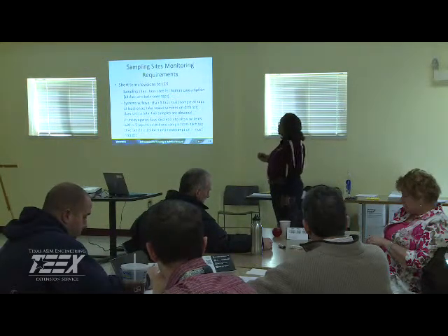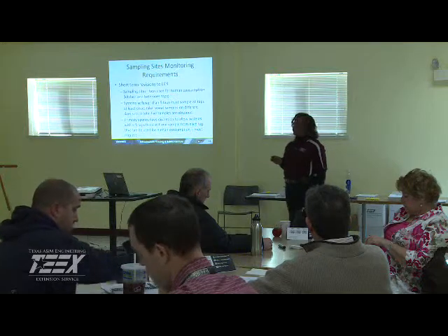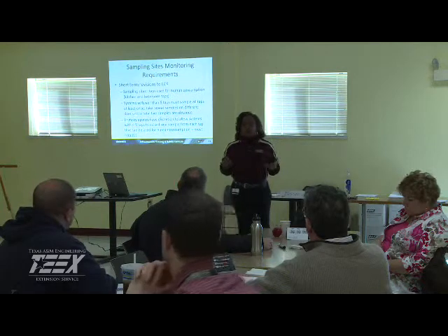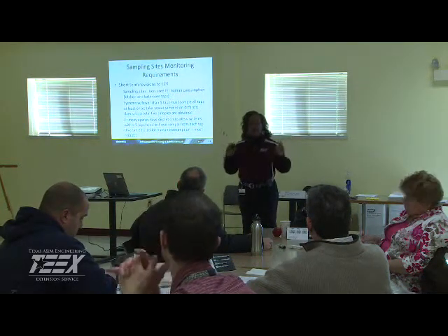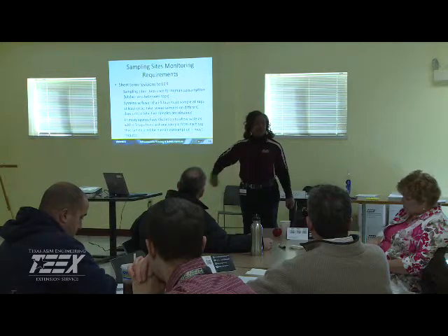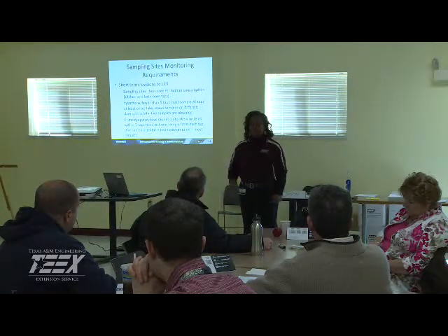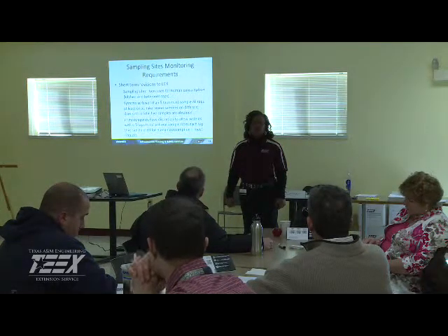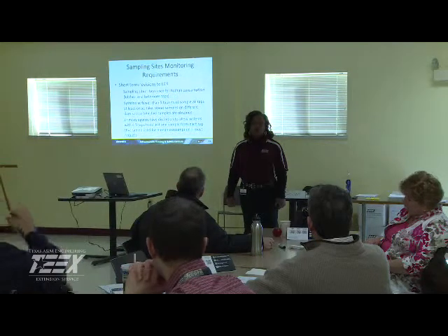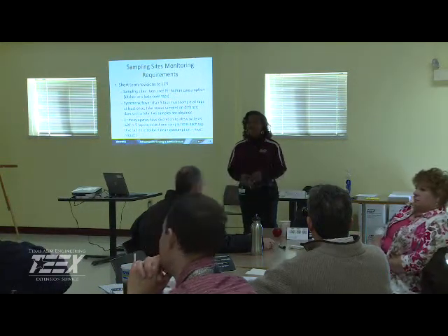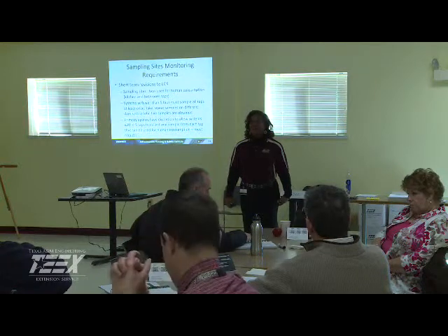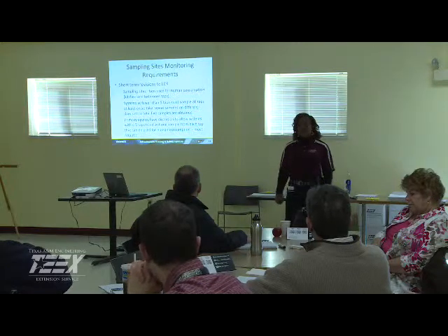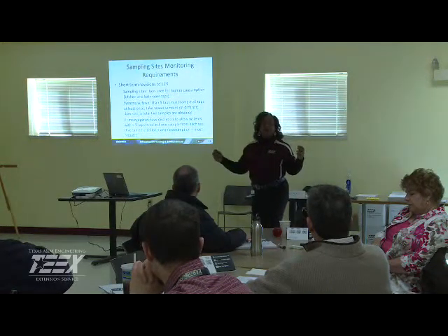All right, let's look at the short-term revisions to the lead and copper rule. Where are we going to pull these samples from? What constitutes an approved sample site? Can I go to the outside little faucet, collect from out there, outside the house? Where do we typically? Huh? Somewhere that's used for human consumption. Very good, Shane, very good. So usually you're looking at a kitchen or bathroom tap. Hot or cold? Cold. Cold.